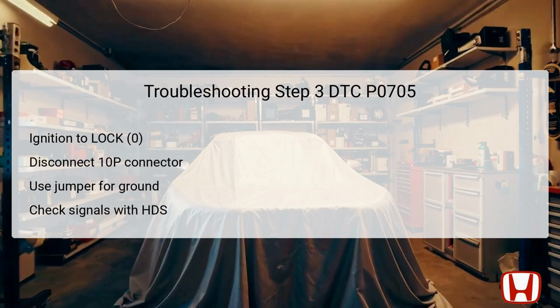This is essential as it isolates the switch from the circuit, allowing for a more accurate diagnosis. Following the disconnection, the next action involves using a jumper wire to ground the terminal in the switch that incorrectly indicated an on state during step 2. This provides a controlled environment to analyze the signal outputs.